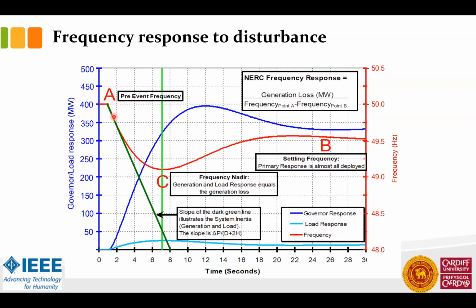Now, during this phase, all the synchronized machines that are on the system provide what we call the inertia response. The synchronized machine will start slowing down because we know that the speed of a synchronized machine is proportional to the frequency. So when the frequency is at 50, it has certain kinetic energy. When its speed comes down, it starts releasing that kinetic energy. That is what we call the inertia response.